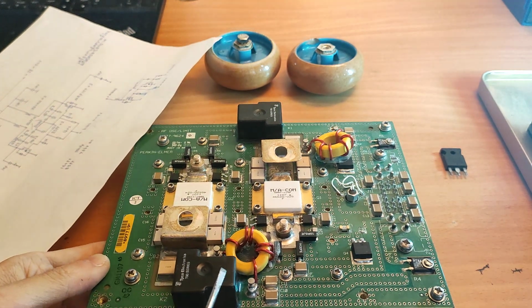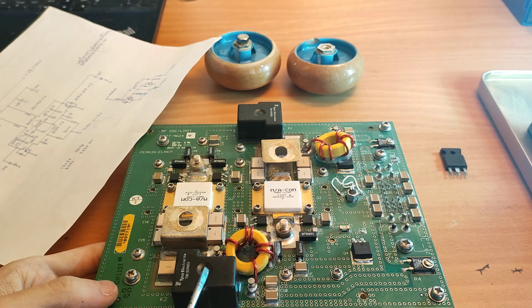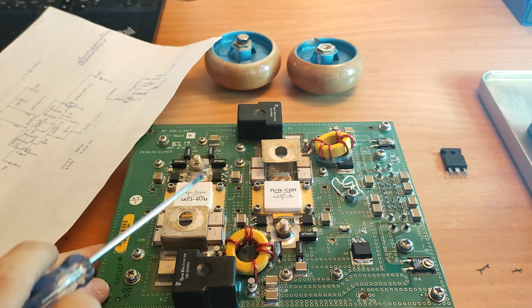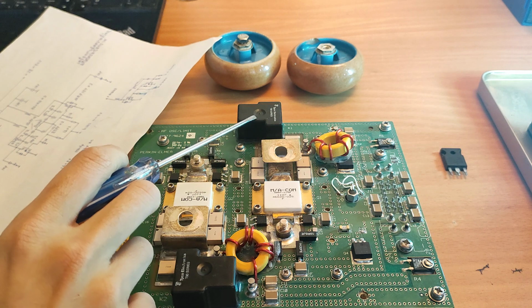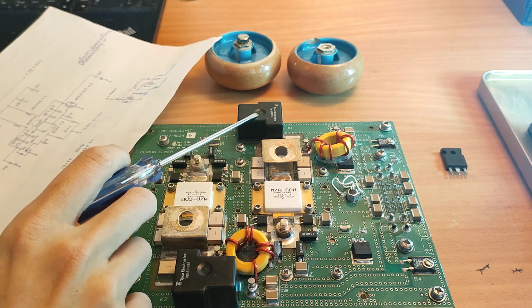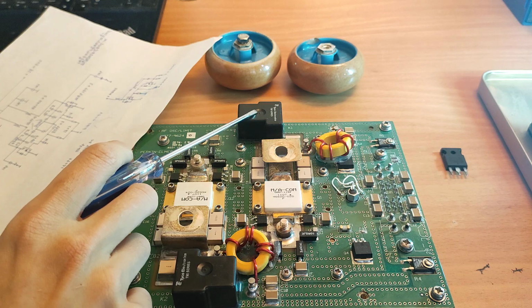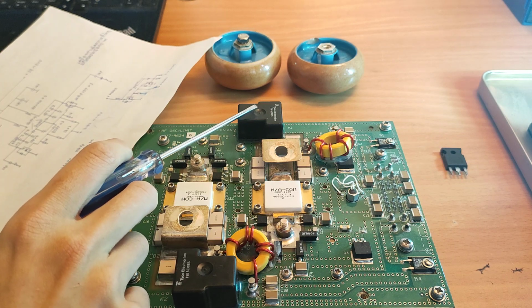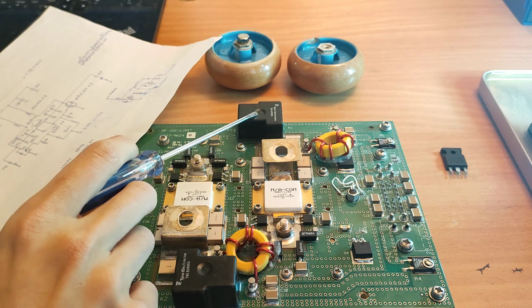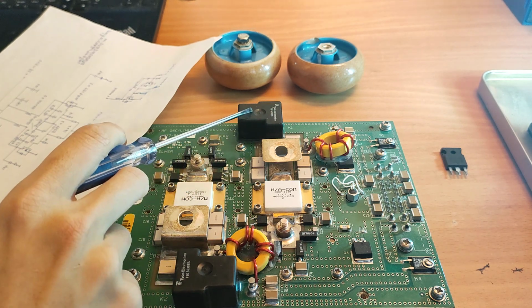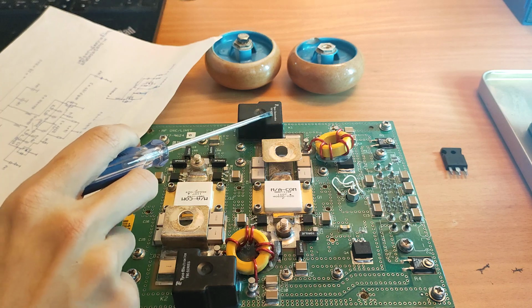That means the manufacturer may have had some failures of the relay during testing because of moisture in the air, right? Because it's an RF circuit, and I think they just use some standard type relay. Maybe they have a larger distance between the connectors. But if that is in an RF amplifier, we need to use some vacuum relays to do this job. They simply use the cheap - maybe not that cheap, but cheaper than a vacuum relay.